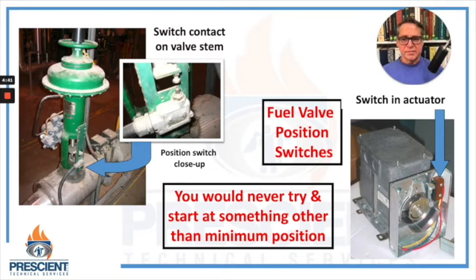I'm showing you that on the left-hand side there. There's a little contact on the valve stem, and it makes that switch. Then on the right-hand side, I'm showing you that there's a position switch buried in an actuator. But again, their function is both the same. They're trying to prevent you from having too large of a gas flow when you light off. Now, low fire gets set at commissioning. It's a very important thing that gets set when a burner is first installed and started up.